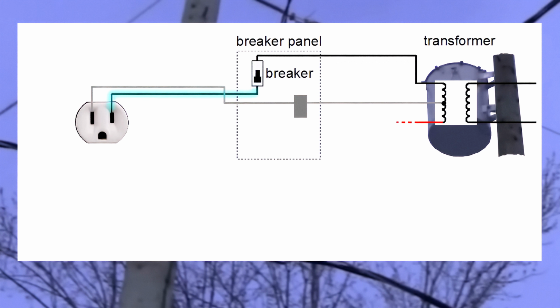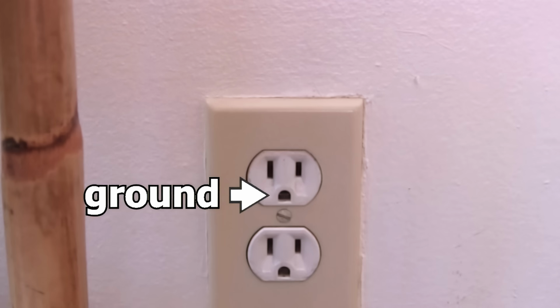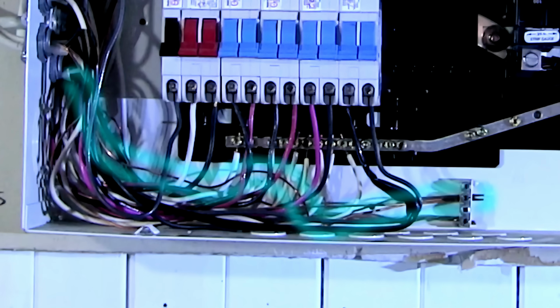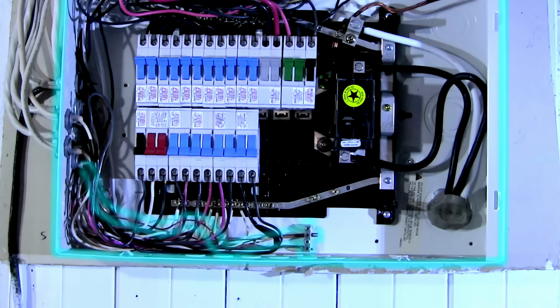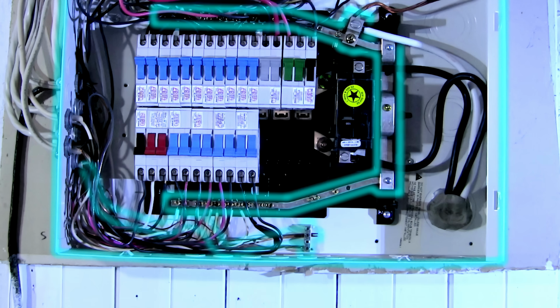This is the path for the hot, or black wire, to the breaker and out to the transformer. And this is the path for the neutral, or white wire, through the breaker panel and out to the transformer. The other side of the transformer is what continues on to the generating station. So where does the ground hole go? It also has a wire that goes to the breaker panel and connects to this other metal bar, which is connected to the breaker panel's metal case. And it's not clear with this panel, but somewhere the case is connected to the neutral bar.